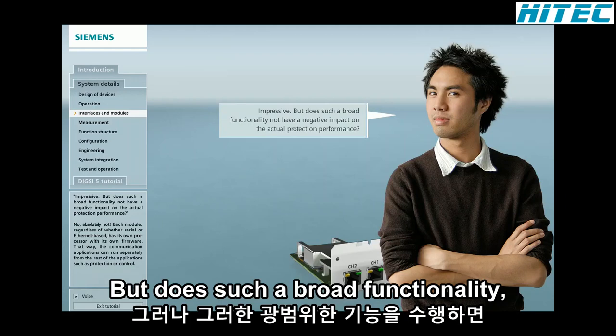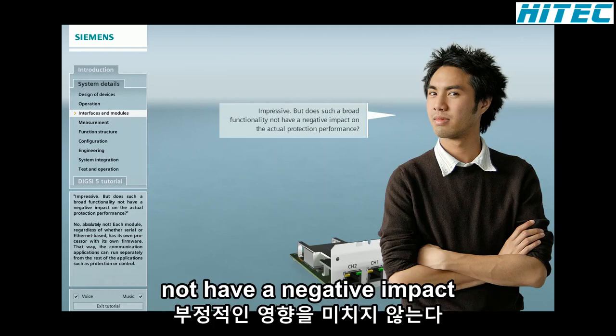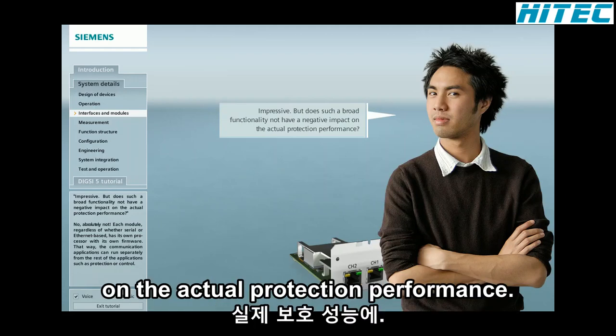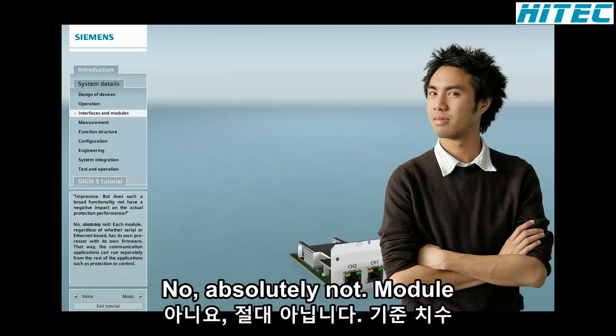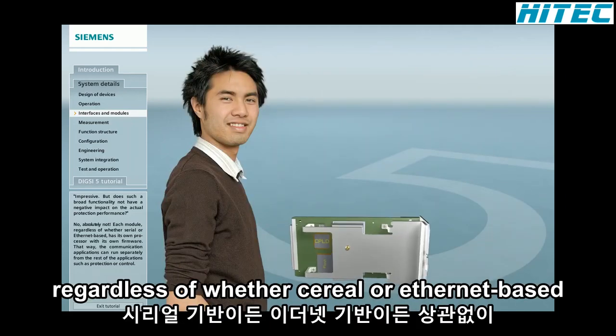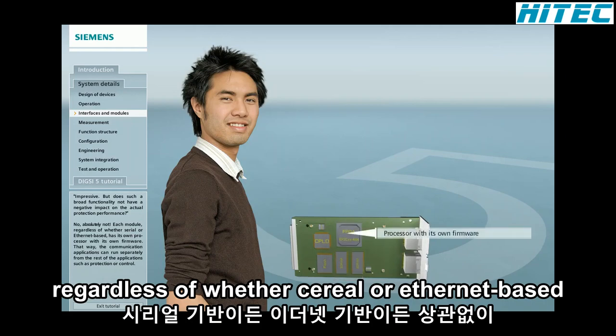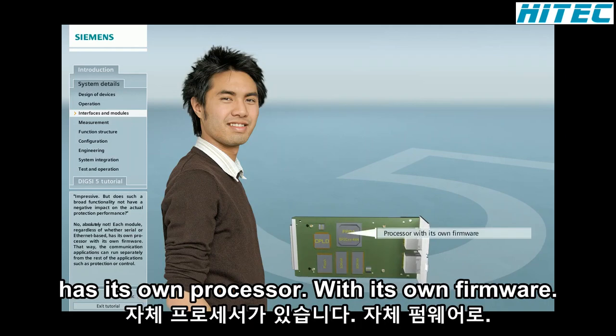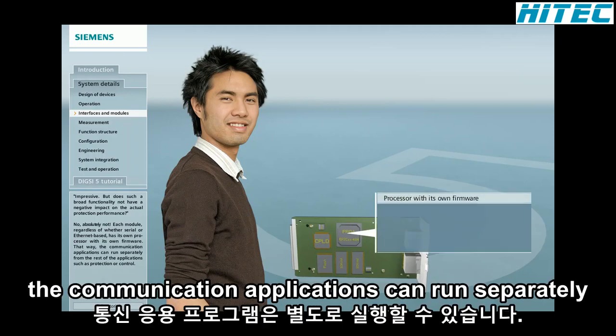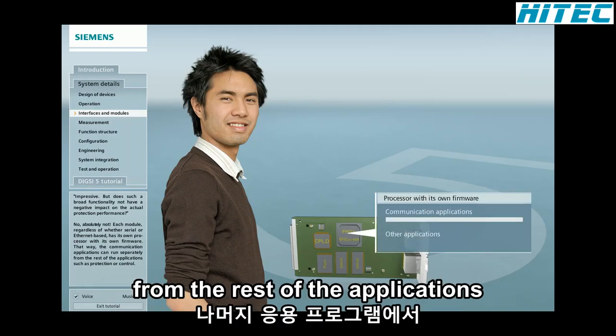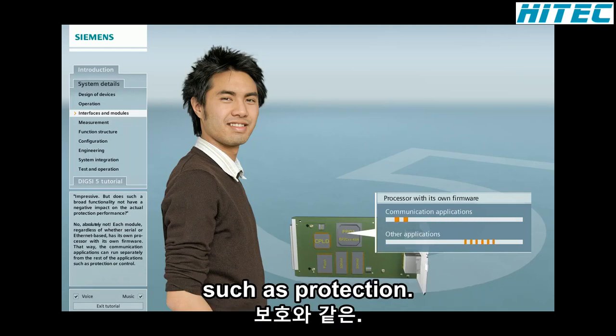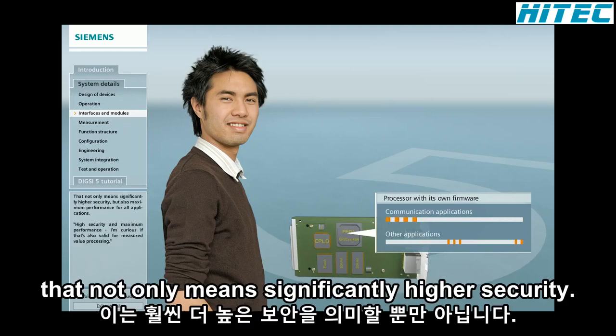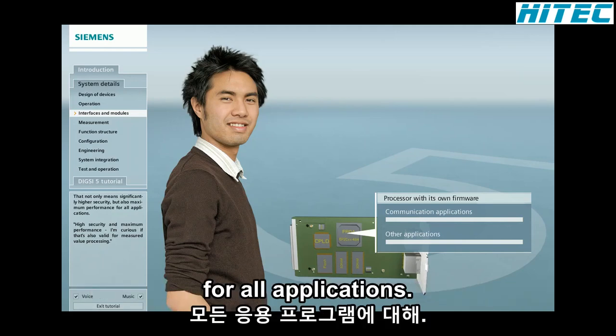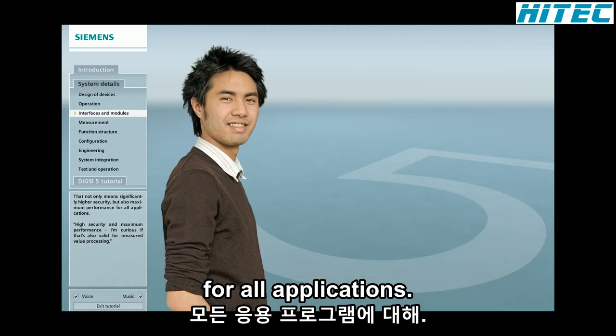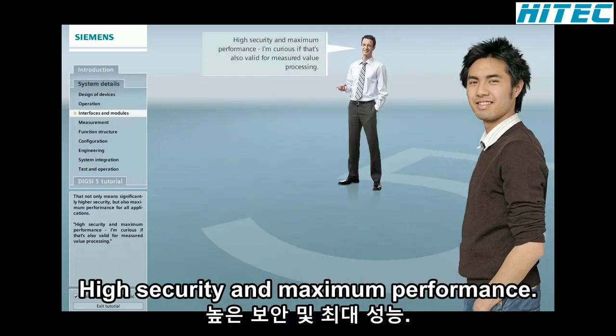Impressive, but does such a broad functionality not have a negative impact on the actual protection performance? No, absolutely not. Each module, regardless of whether serial or Ethernet-based, has its own processor with its own firmware. That way, the communication applications can run separately from the rest of the applications, such as protection or control. That not only means significantly higher security, but also maximum performance for all applications. High security and maximum performance.